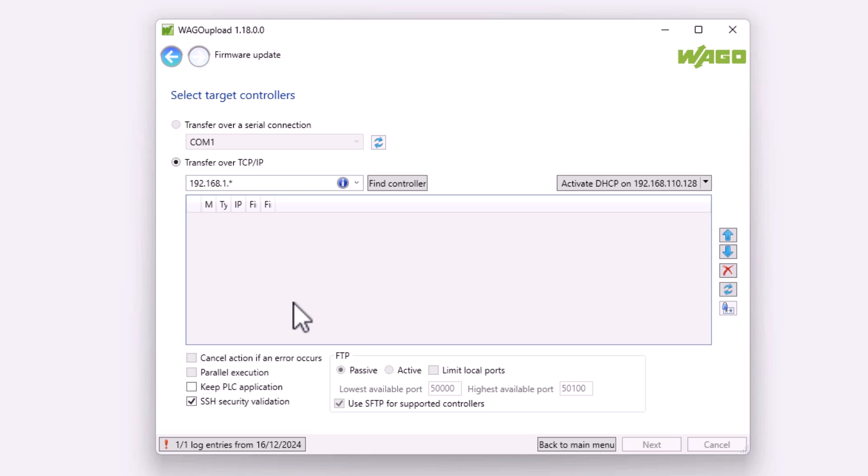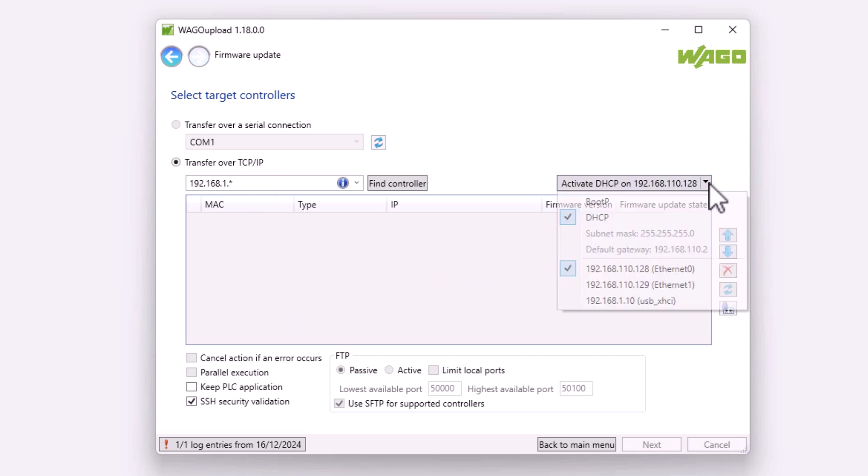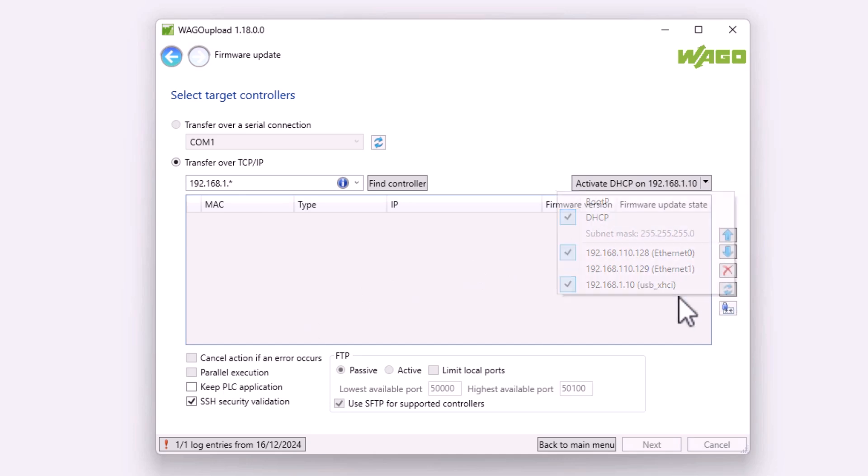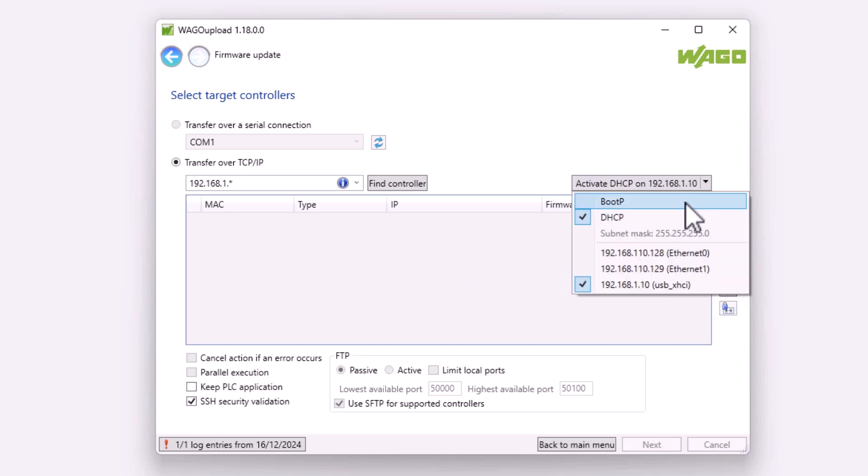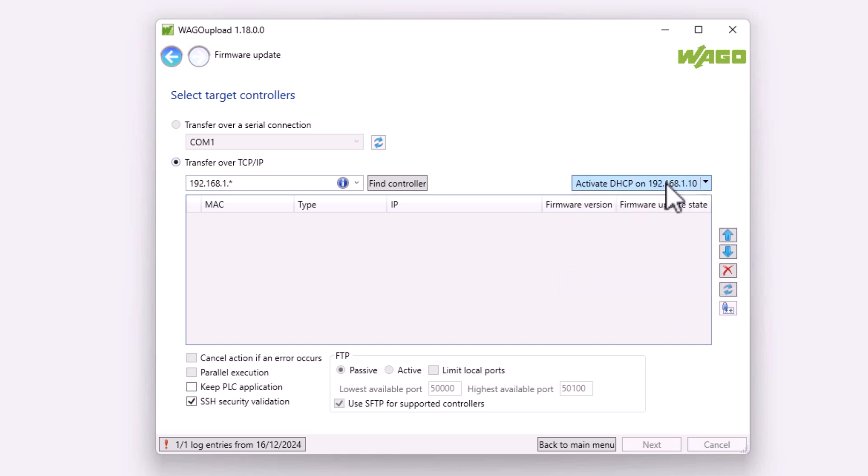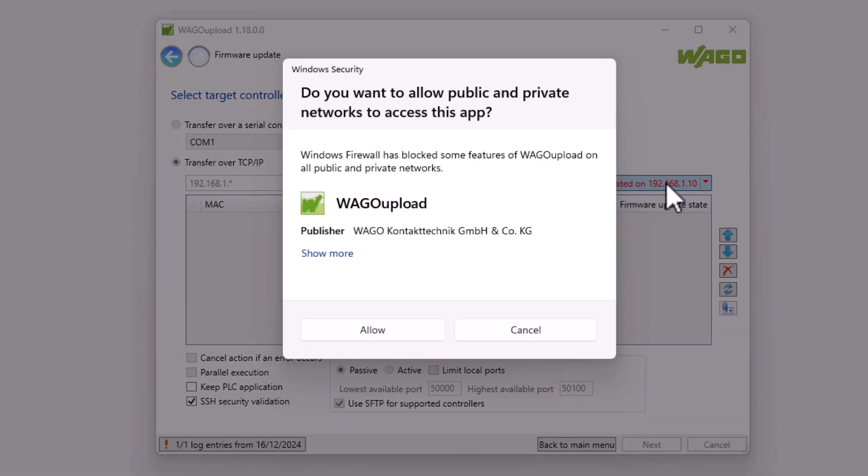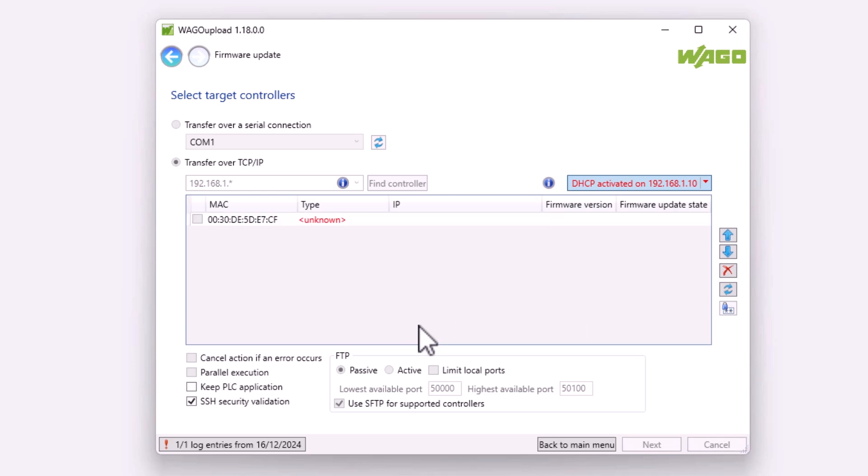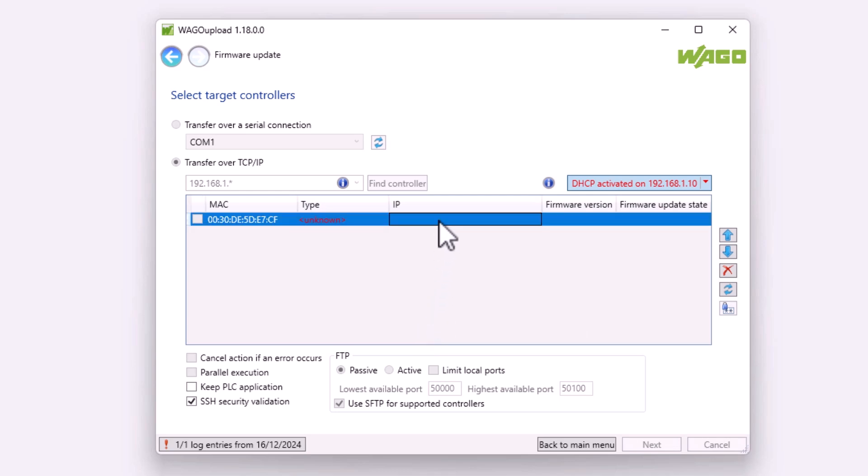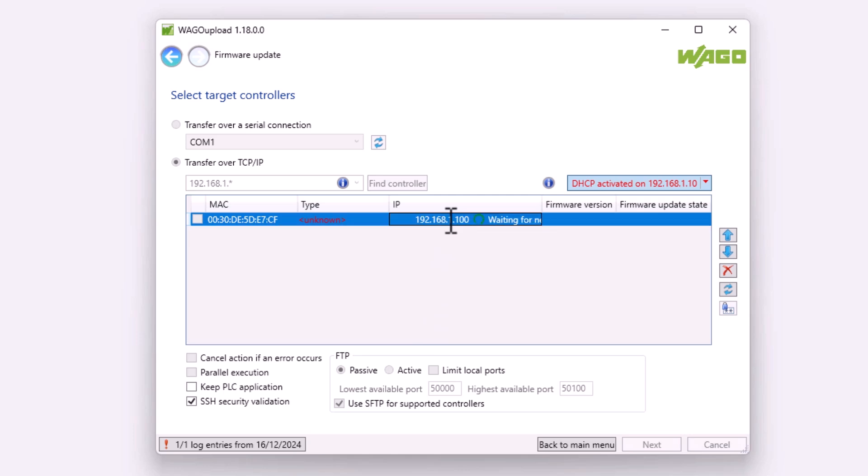We want to access the controller via the Ethernet interface, so we select Transfer via TCP IP. On the right-hand side is the drop-down menu to enable DHCP. First select the Ethernet port on the PC to which the controller is connected and tick the box for DHCP. Click on the grey box next to the arrow to activate DHCP. The text will now turn red and after a few seconds the controller will be displayed with its MAC address. Unlike what you are used to with your home router for example, an IP address is not assigned automatically. Instead you can enter an IP address manually. This means that although we are using the DHCP protocol, we are manually assigning the IP address, with all the advantages and disadvantages that this brings.